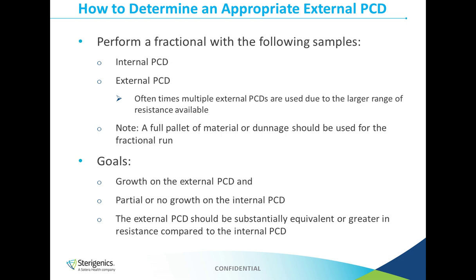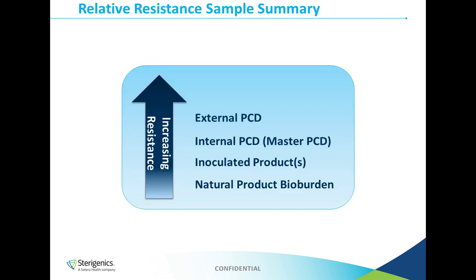Now on the fractional run, you're going to want to make sure you get growth on that external PCD, and you're going to need partial or no growth on that internal PCD. This would show you that that external PCD is substantially equivalent or greater in resistance compared to that internal PCD. Now, when you do this comparison, you don't always want to choose the external PCD that is significantly greater in resistance than your internal PCD. The reason for that is, if you choose a PCD that's significantly more resistant, you may be challenging your process more than you need to, which could result in an extended processing time and longer heat duration. So you want to make sure it's at least somewhat similar in resistance while still being equal or greater.